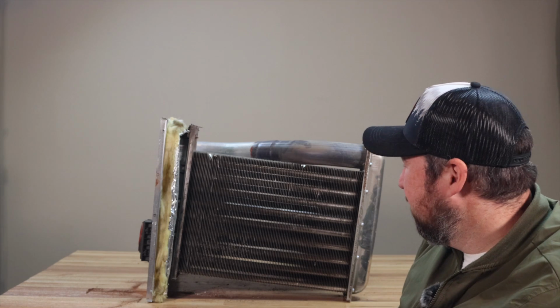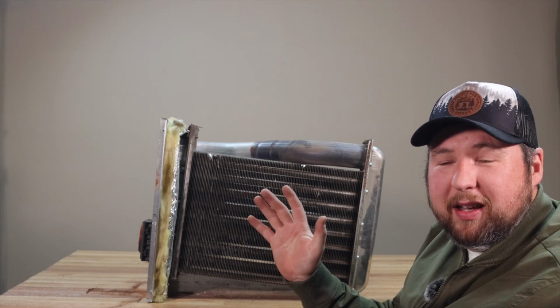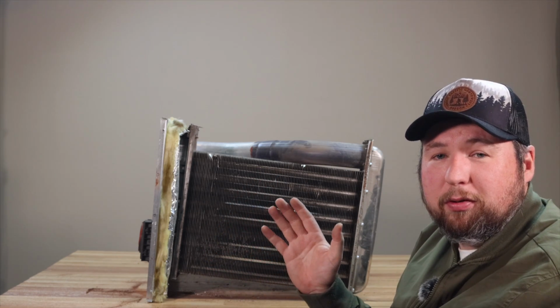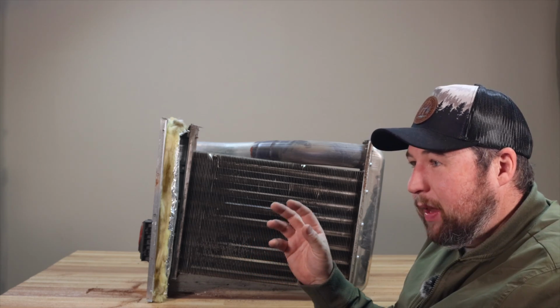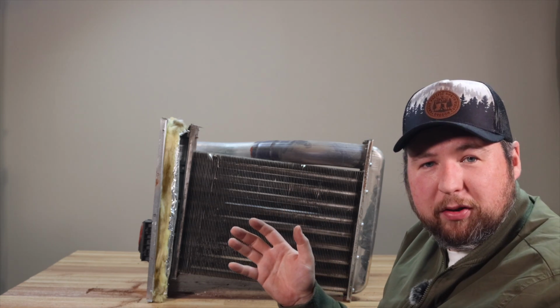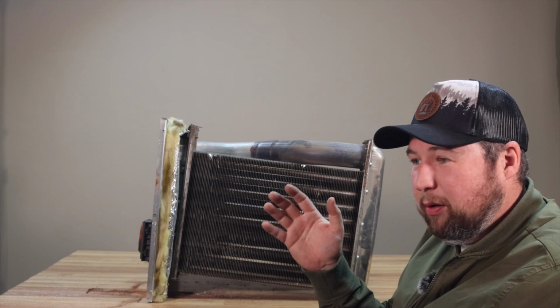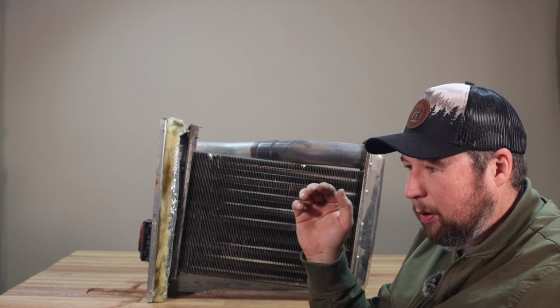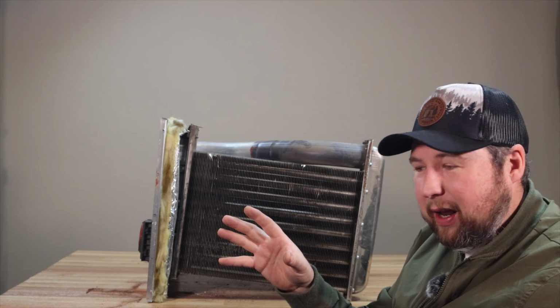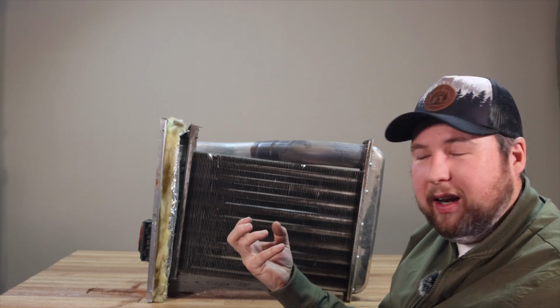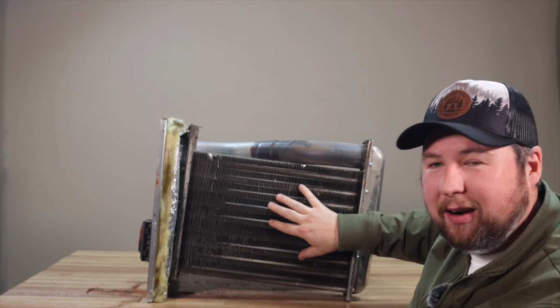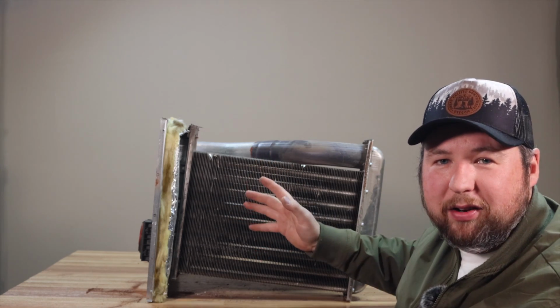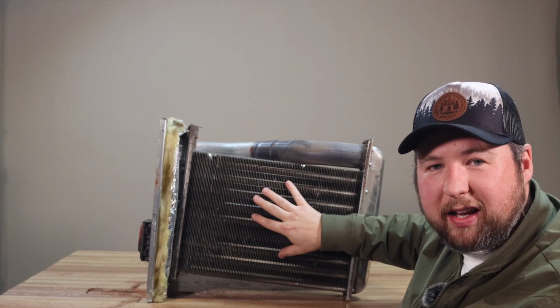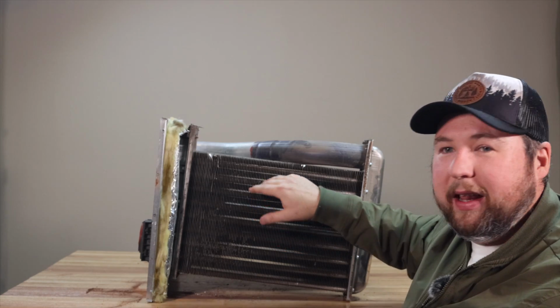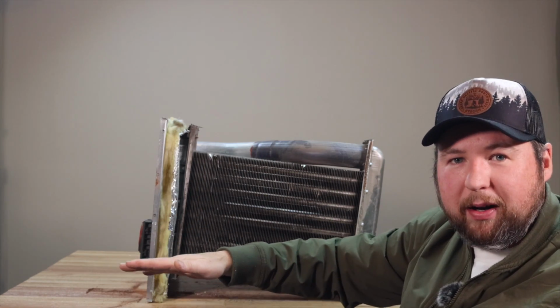That's crazy, right? Now, because the exhaust temperatures are so much lower, any moisture in there, because one of the products of combustion is moisture, right? Because you have moisture in the air, and when you're burning, you're going to be vaporizing any moisture in the air, right? And as it gets cold, it's going to condensate and it's going to collect inside here. That's why you have an entire drainage system, because it'll condensate in the secondary heat exchanger and then it goes through a drainage system to get rid of it.